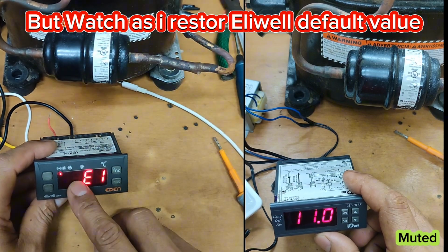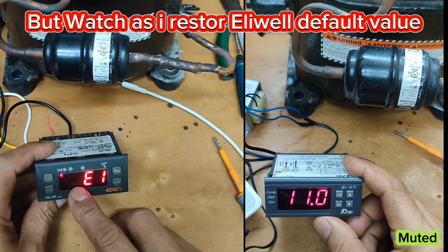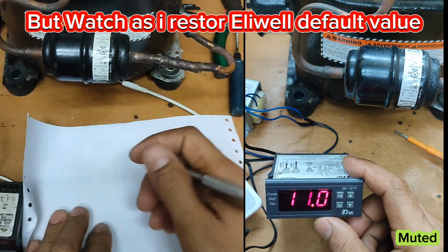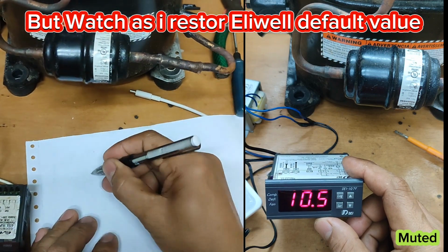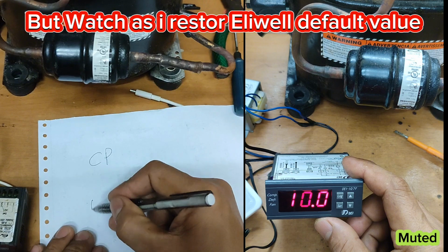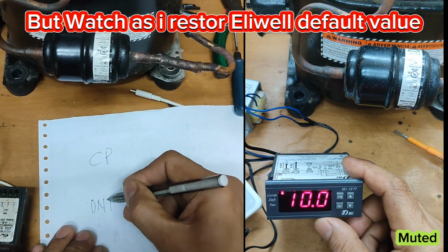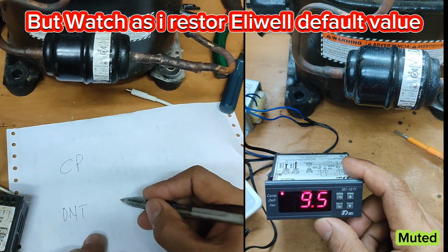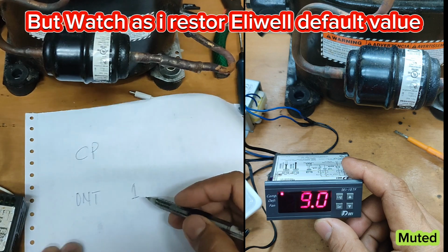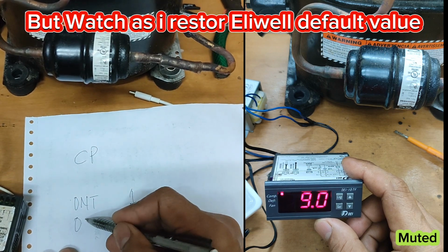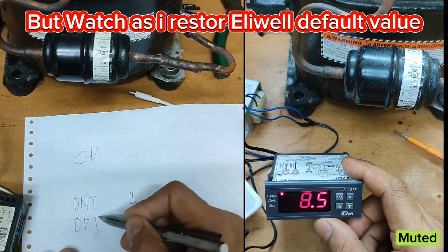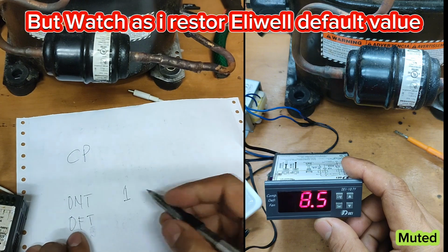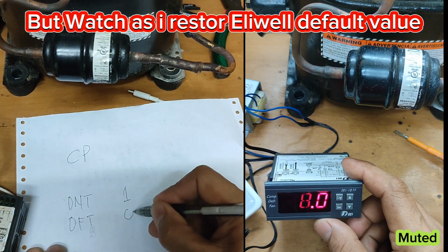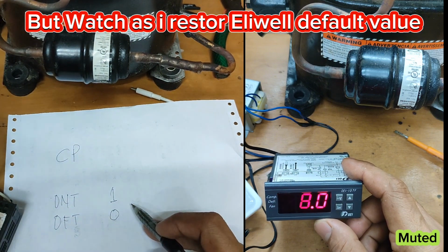The manual is not supposed to be programmed with their OFT and CP folder this way. Their ON time during faulty probe is set to 1, and then the OFT, off time during faulty probe, is set to 0. This is in accordance with their manual.